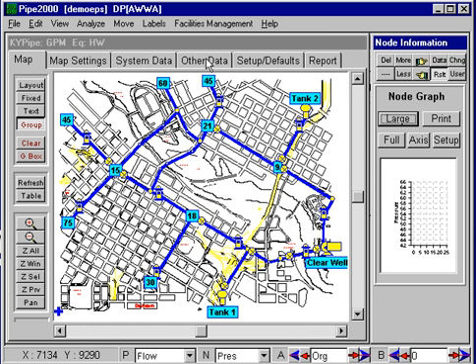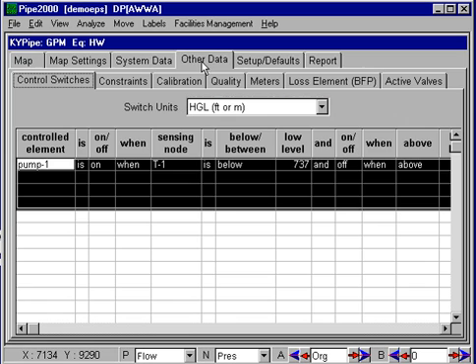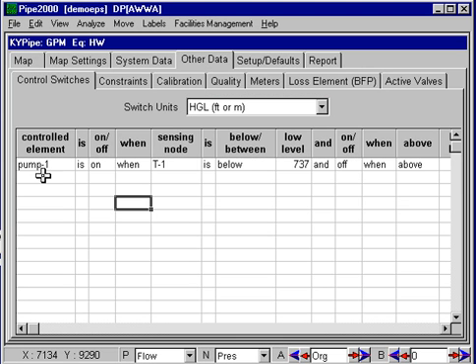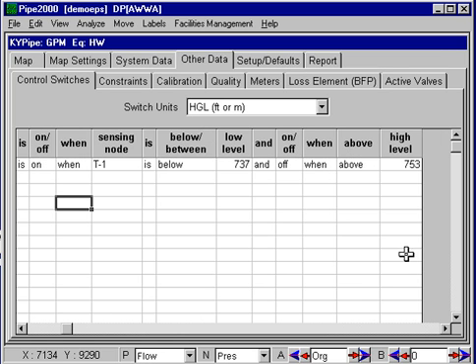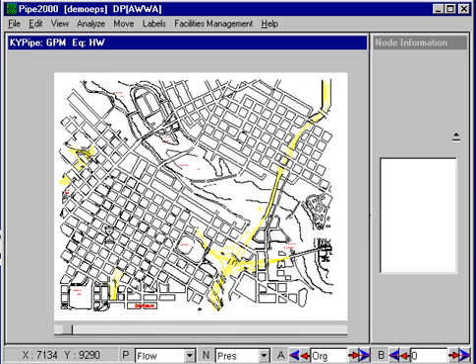This is set up under Other Data, Control Switches. The pump is on when the tank goes below 737 and it's off when it gets above 753. That's the control switch data that's often used for extended period simulation.